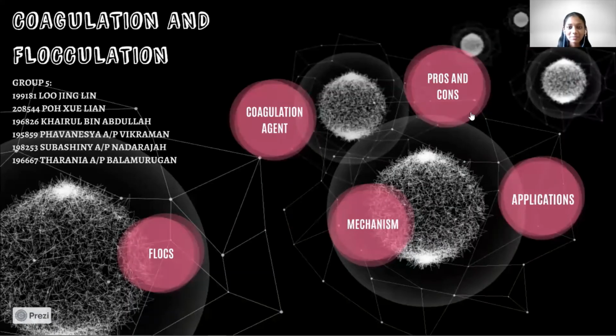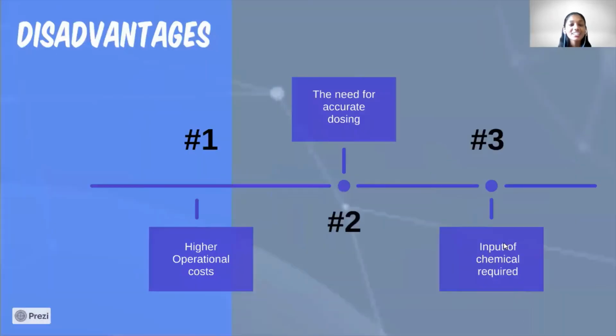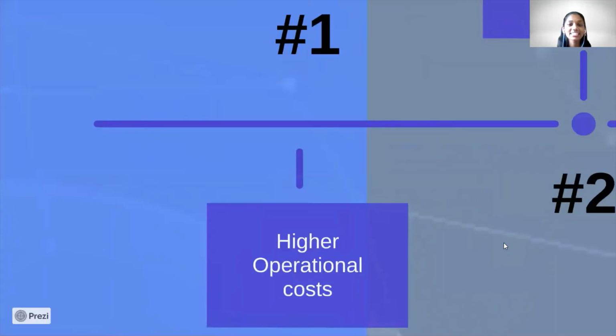So for my part, I will be presenting the disadvantages of the coagulation and flocculation process. A major disadvantage of this technique is the operational cost. In some cases, considerable quantities of coagulant and flocculant are needed to achieve the required level of flocculation. A certain quantity of physical chemical sludge is also formed, which is normally processed externally. This cost can escalate, particularly with large volumes of wastewater.